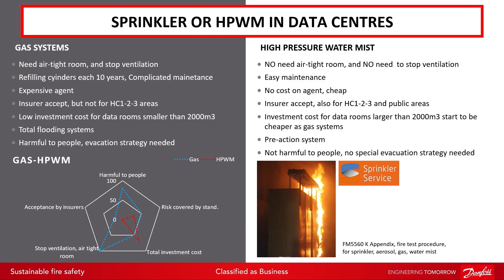It's interesting that FM, the American standard, the new ones, already prescribe how to make a one-to-one scale fire test for data centers—not only for water mist, I'm trying not to focus only on water mist, but also talk about other systems. Inside this FM approval, you can have a sprinkler system, which is legally accepted by FM—don't ask me why, but there's a fire test for it. Of course aerosol is accepted, gas is accepted, and high pressure water mist is accepted.